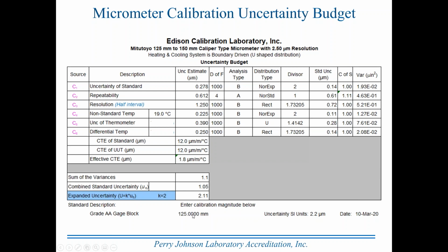Right here, you'll see entered the length of the standard. We were calibrating at a length of 125 millimeters. So the calculation was done based on the effective coefficient of thermal expansion to adjust that 125. And we wind up with uncertainty expressed in SI units, 2.2 micrometers.